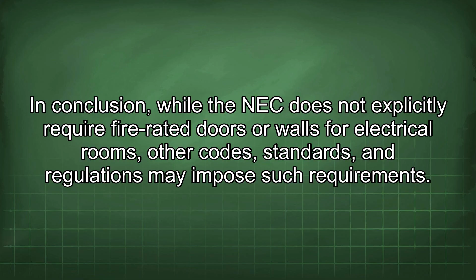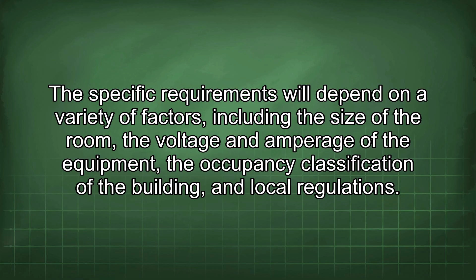In conclusion, while the NEC does not explicitly require fire-rated doors or walls for electrical rooms, other codes, standards, and regulations may impose such requirements. The specific requirements will depend on a variety of factors, including the size of the room, the voltage and amperage of the equipment, the occupancy classification of the building, and local regulations.